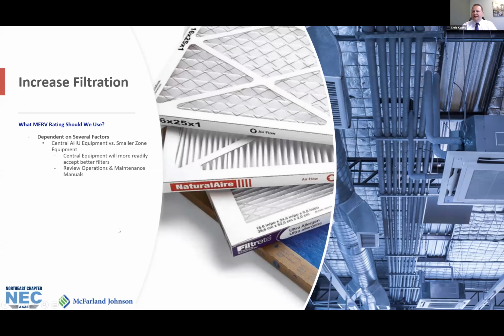Your air filter is a literal barrier between your HVAC system and the remainder of the air distribution system, and it slows the ability of the air to get pulled or pushed through the ductwork of your system. So how much your HVAC's airflow is slowed by a filter is directly related to its pressure drop. And pressure drop will vary by filters. Filters that are more tightly woven and typically more efficient make it harder for air to pass through them. This is going to create a decrease in the airflow and a higher pressure drop. So what I recommend, you want to find that balance to ensure your HVAC system can handle filter upgrades without negative impacts to pressure differentials or airflow rates prior to changing your filters.